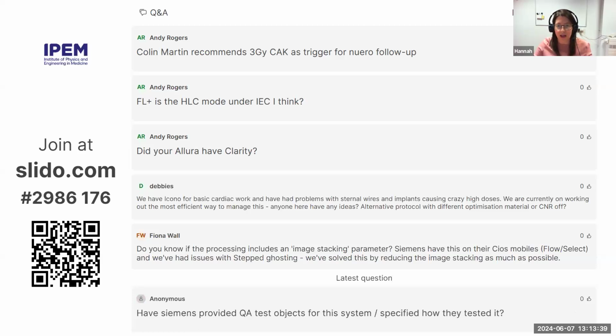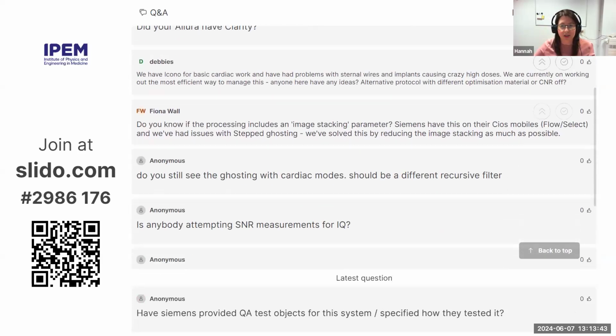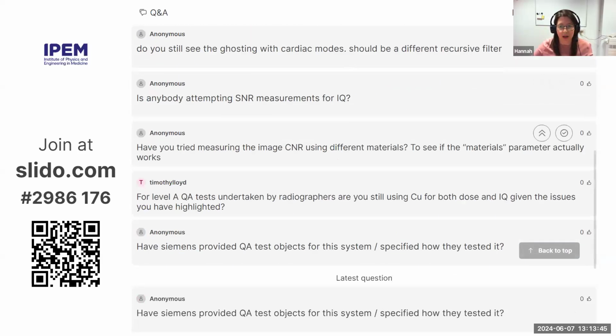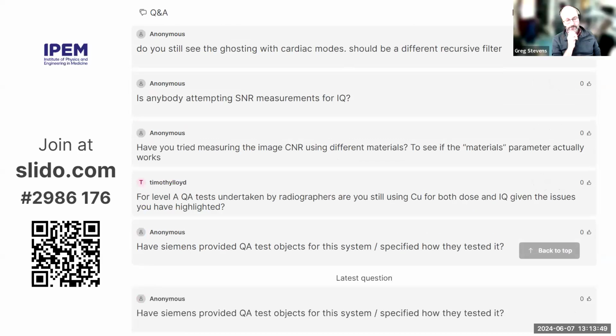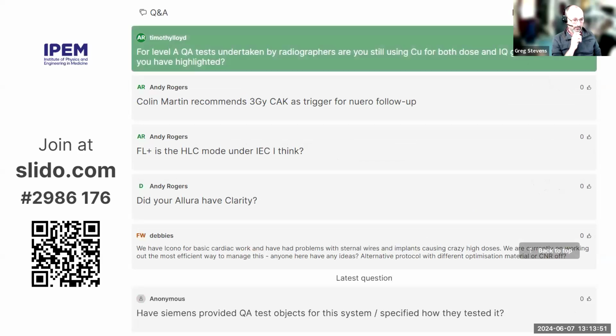So for Level A QA tests that have been undertaken by radiographers, are you still using copper for both dose and image quality, given the issues you highlighted? No, definitely not. We got them some perspex, and that's been nice and stable, and they've got really good reproducibility. So that's what we're sticking with.